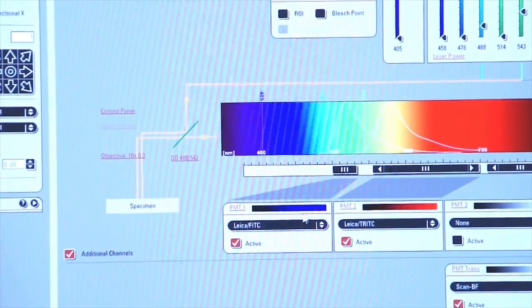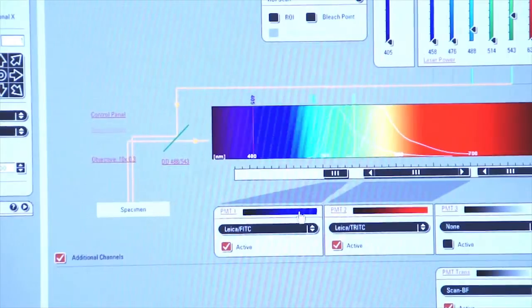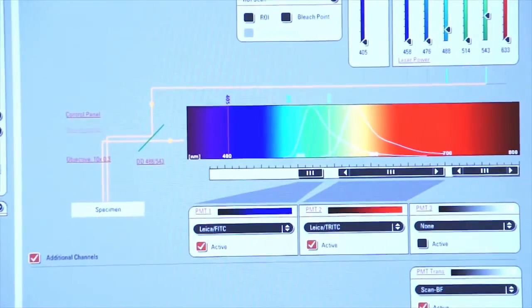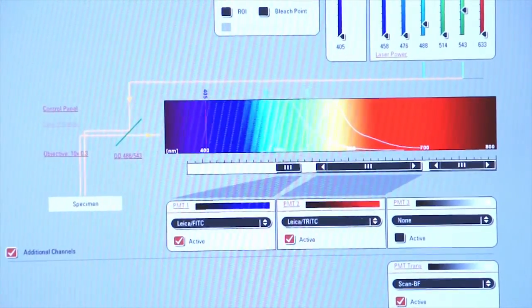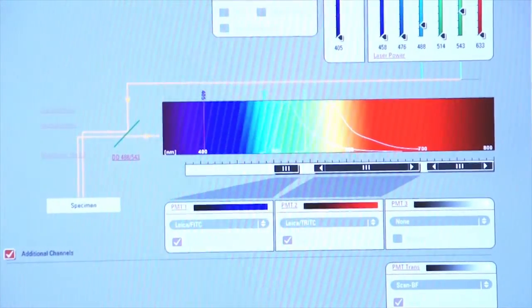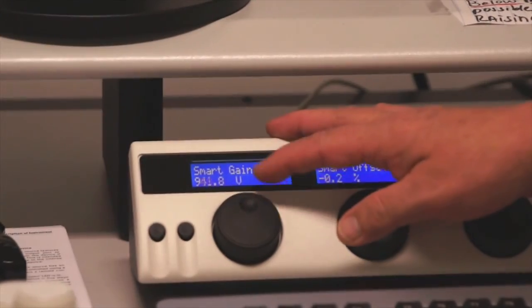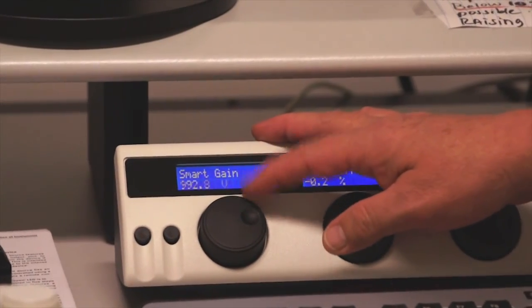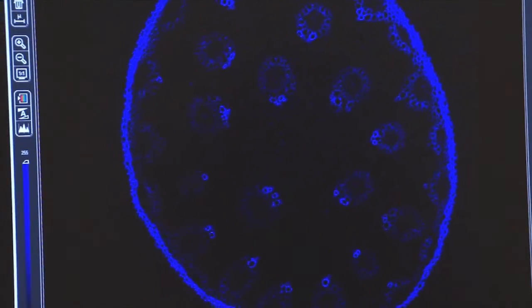And now as you can see, the color here has changed. And so my output for this screen, if I click on live, will be blue. Now you can see that it's a blue image. And I can increase the brightness by either controlling the gain or I can widen the photo multiplier tube or increase the laser power.